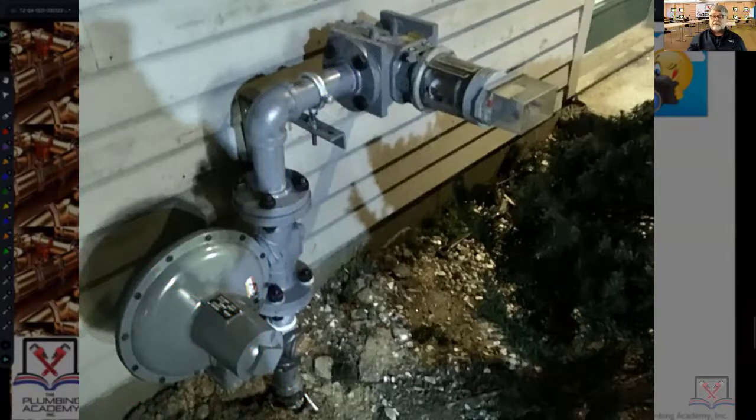When doing gas piping or assessing a gas problem, you can have one of two things: in a low pressure gas system you may not have enough gas pressure; in an elevated gas pressure system with a service regulator you could potentially have too much gas pressure. You want the awareness to ask these questions and use that experience to make a sound assessment when walking into a building to do work on, change, or install gas equipment brand new. If you're not looking at this, you really don't demonstrate the ability to survey a situation.